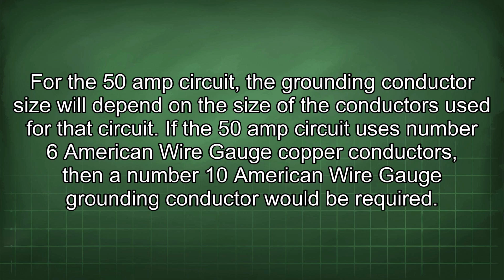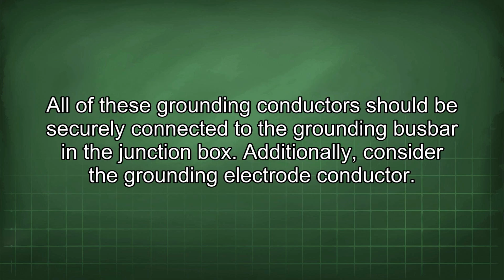For the 50 amp circuit, the grounding conductor size will depend on the size of the conductors used for that circuit. If the 50 amp circuit uses number 6 American wire gauge copper conductors, then a number 10 American wire gauge grounding conductor would be required. All of these grounding conductors should be securely connected to the grounding busbar in the junction box. Additionally, consider the grounding electrode conductor.